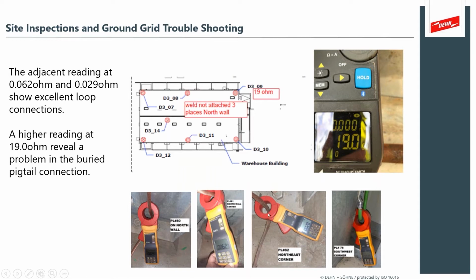And that's what's really nice about meters of this type, that it's essentially an active ping. It actually injects a ping into the system, almost like a sonar, and then it listens for that connection. And it tells you that it's a well-installed loop. And again, what it's helping you do is it's helping you interpret the buried connections. You can see that there's an above grade connection, but you don't get to see the buried connections. And this gives the customer a very good indication that the buried system is suitable for his application.